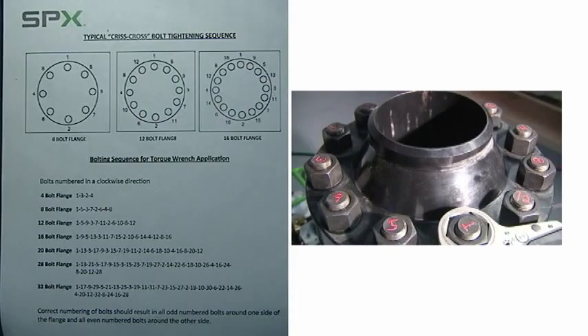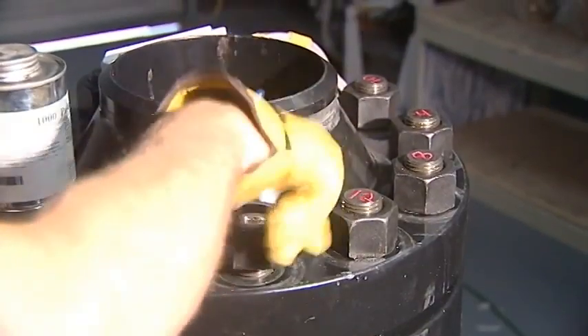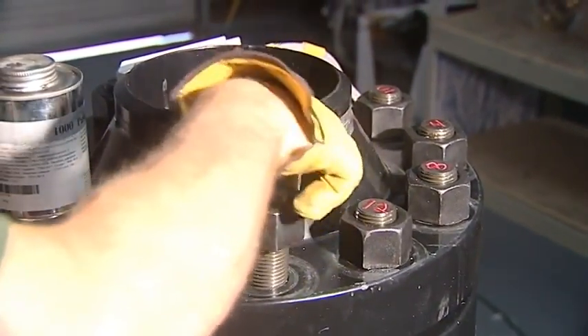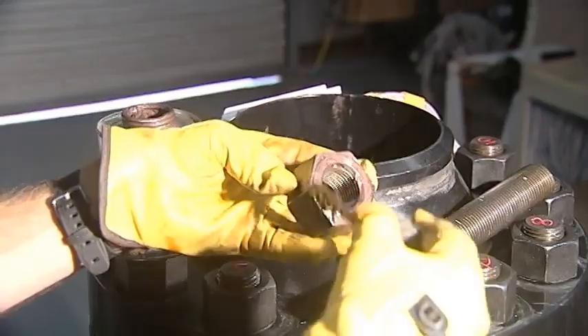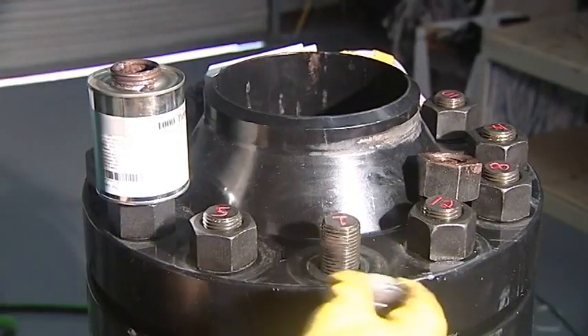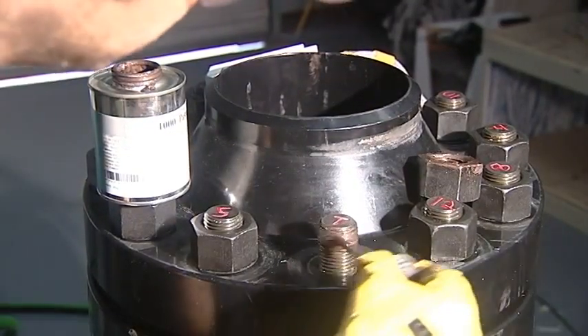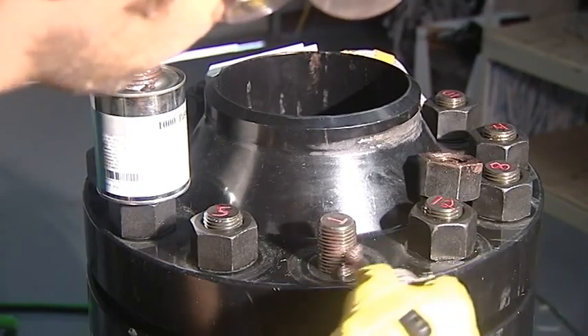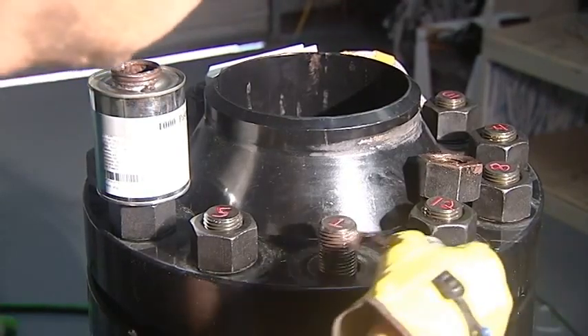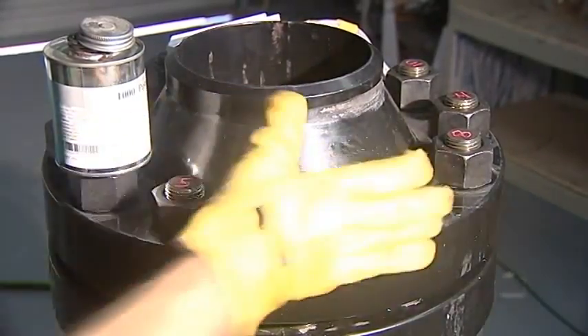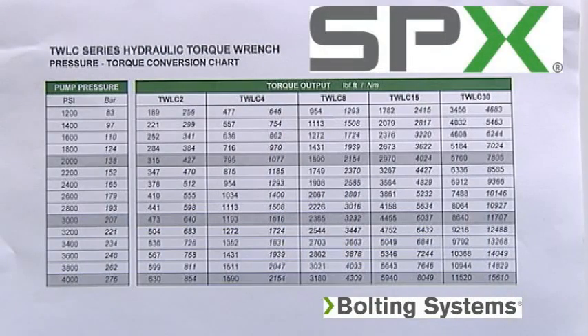Proper bolting sequence pattern and foot-pound requirements are also essential to ensure proper load is applied, so it is important to check with your customer or company on any specific procedures relating to bolting the joint, including the type of lubricant that may be required when installing the studs and the nuts. Once you have been given load requirements, you can check the tool torque conversion chart for the proper PSI and foot-pound requirements based on the tool you are using.